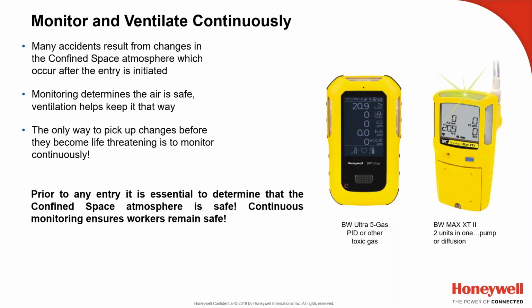Previously, in 1993, when the standard first came out, the technological capabilities at that time with gas detection, runtime, and various other factors meant it said to periodically monitor the atmosphere. That bar was raised in 2015, when the recommendation came out to continuously monitor unless you absolutely can't. That change was driven by the technological advances in gas detectors.